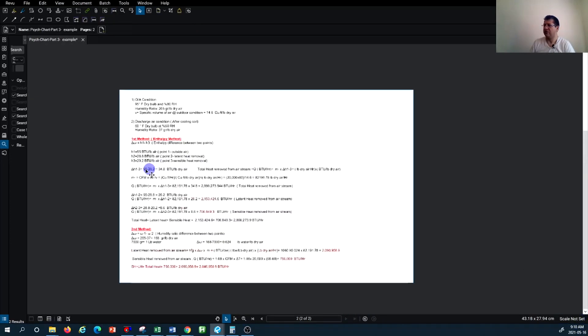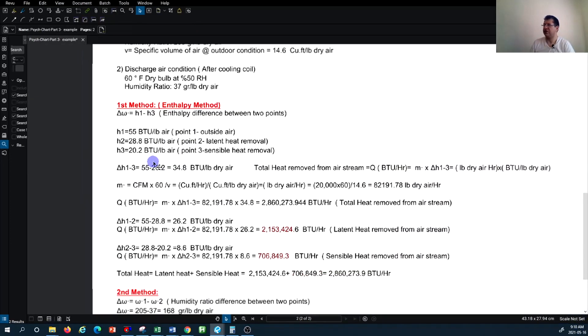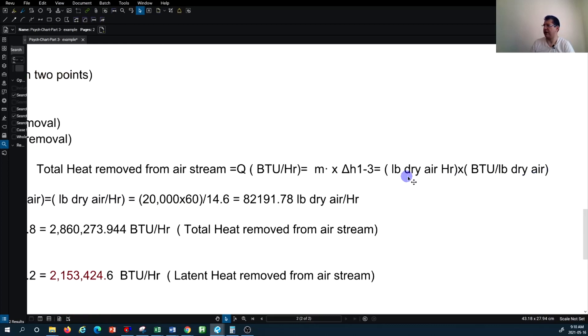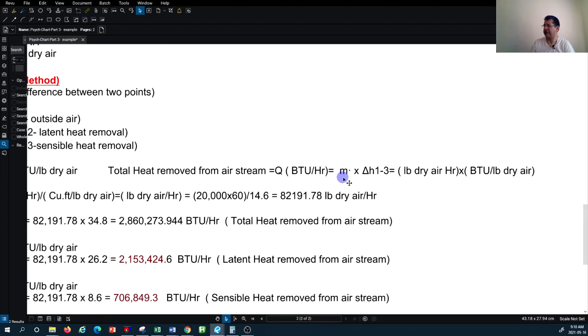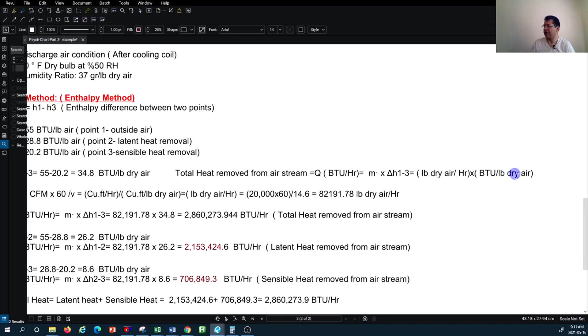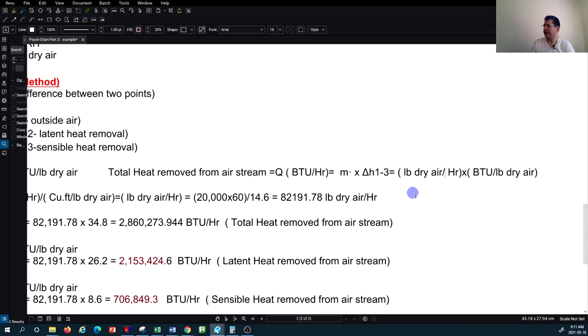You can easily calculate total heat removal by multiplying the mass rate of air at Point 1 by the enthalpy difference between Point 1 and Point 3. Checking the units: mass rate in pounds of dry air per hour multiplied by BTU per pound of dry air cancels out, giving BTU per hour as the total.